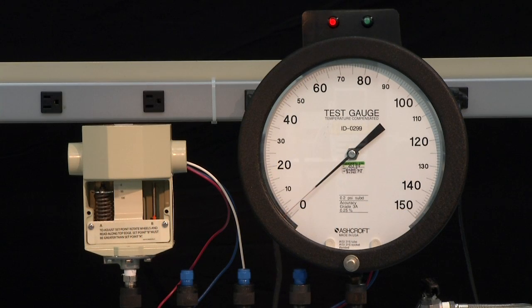This should be done three times. So the first step is to take the switch from zero up to the 80 PSI target and leave it there. Bring the pressure up to 80 PSI and lock it off.